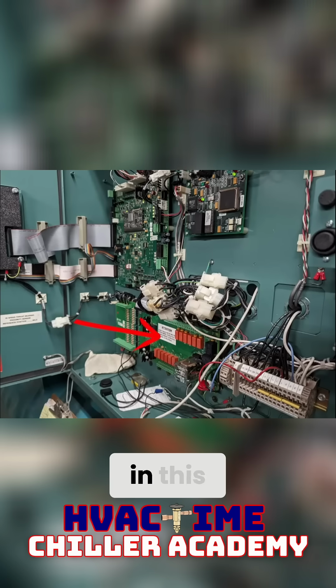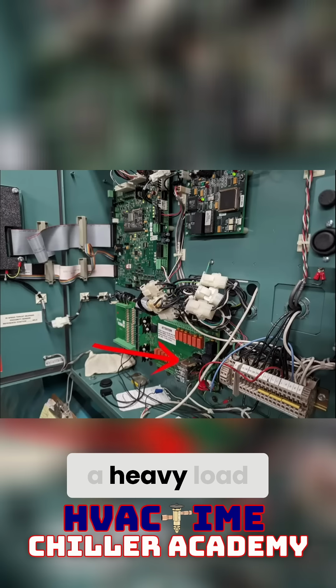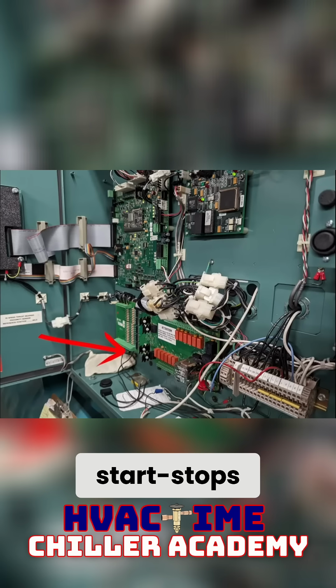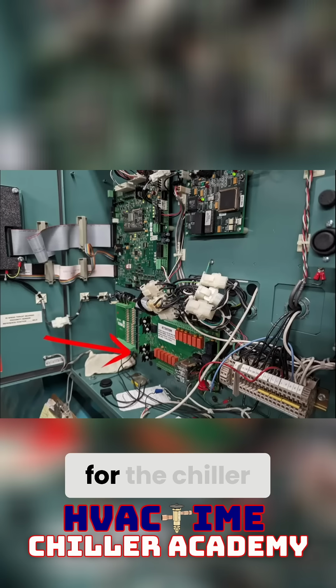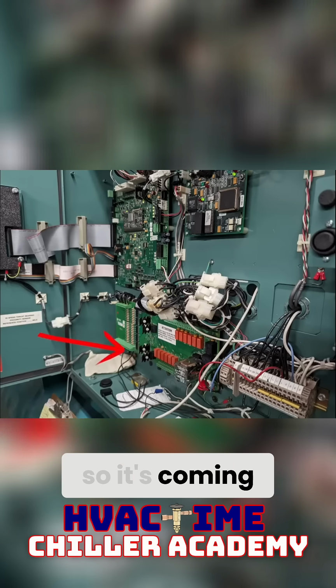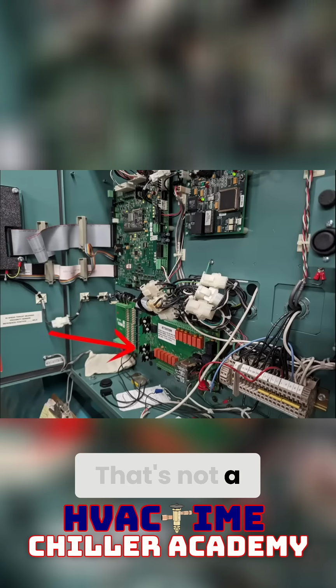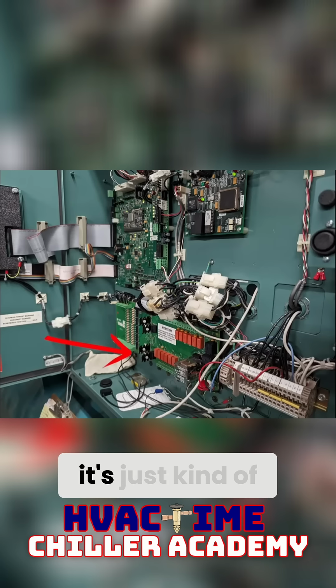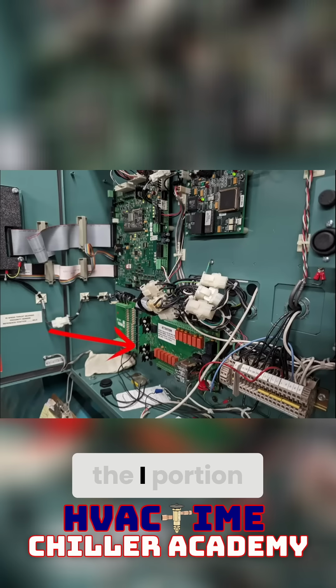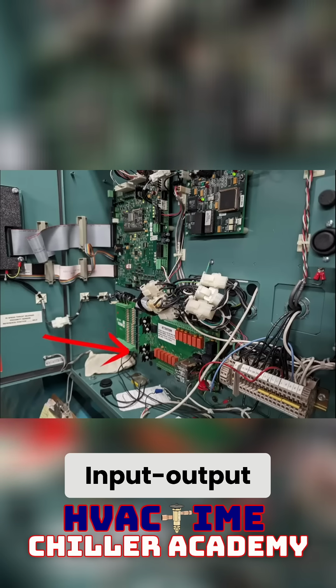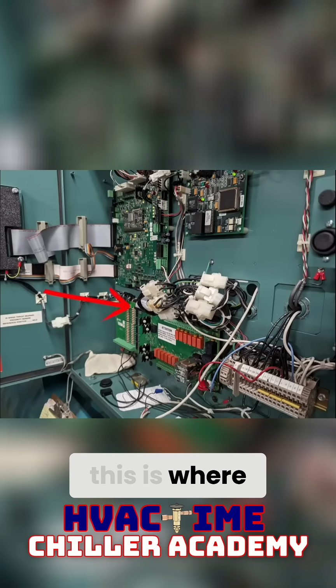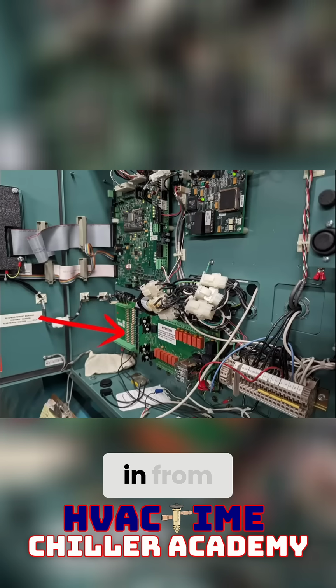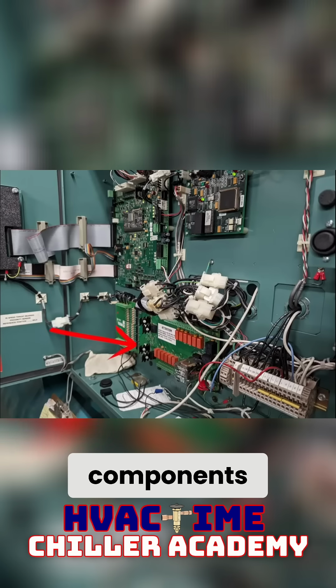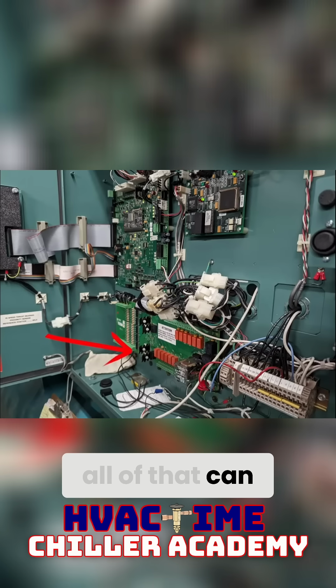Not everything on this I/O board is, say, a heavy load. For example, your start stops. These are your start stops for the chiller from the automation system. So it's coming in, tying in here. That's not a major load, but that's also where it's just the I portion, the input output board. So this is where your inputs coming in from other components, the automation system, all of that can come in here.